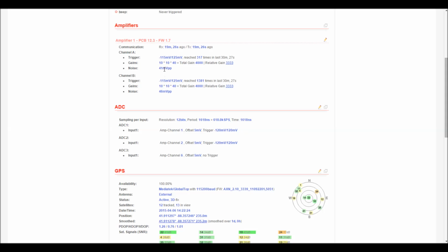But you want a very good margin of difference between your currently operating noise value and your threshold value. The lightning impulses tend to be pretty high amplitude, so this will jump up very quickly to overcome this threshold value on a valid lightning signal.